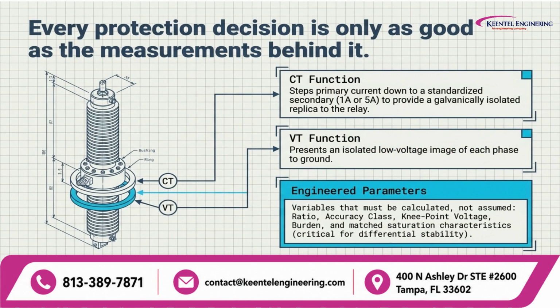Every protection decision is only as good as the measurements behind it. Let's start with the current transformer, or CT. The CT steps the primary current down to a standardized secondary value, typically 1 ampere or 5 amperes. This provides the relay with a galvanically isolated representation of the high current primary system. The voltage transformer, or VT, provides an isolated low-voltage representation of the phase-to-ground voltage. But these devices cannot simply be selected based on their nominal ratio.